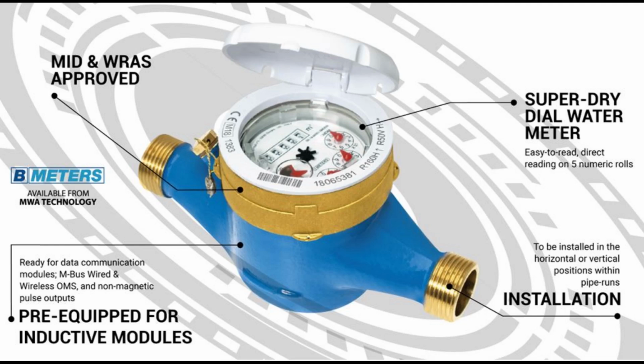1,234,567 gallons. In the United States, most utilities bill only to the nearest 100 or 1,000 gallons, 10 to 100 cubic feet, 1 to 10 cubic meters, and often only read the leftmost 4 or 5 numbers on the display wheels. Using the above example, they would read and bill 1,234, rounding to 1,234,000 gallons based on a 1,000-gallon billing resolution.